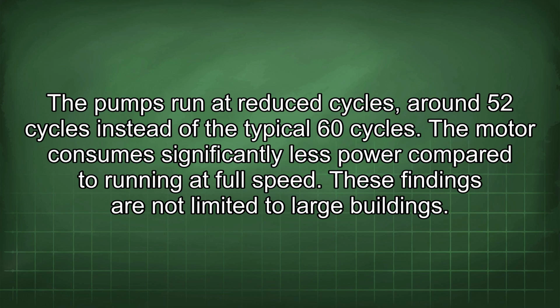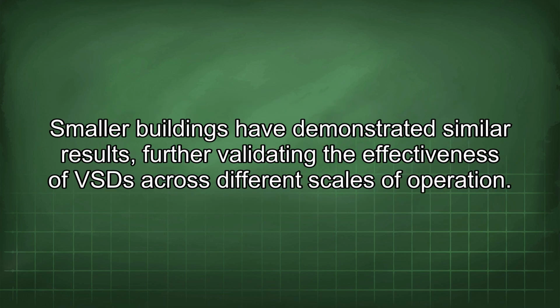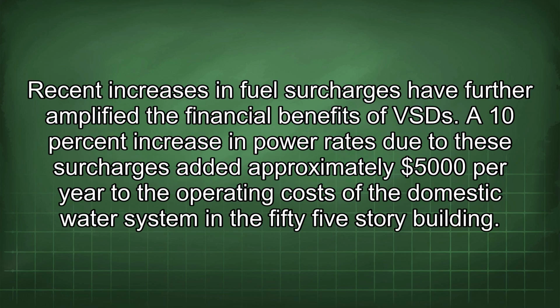These findings are not limited to large buildings. Smaller buildings have demonstrated similar results, further validating the effectiveness of VSD across different scales of operation. Recent increases in fuel surcharges have further amplified the financial benefits of VSD. A 10% increase in power rates due to these surcharges added approximately $5,000 per year to the operating costs of the domestic water system in the 55-story building.